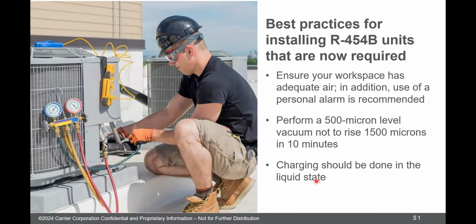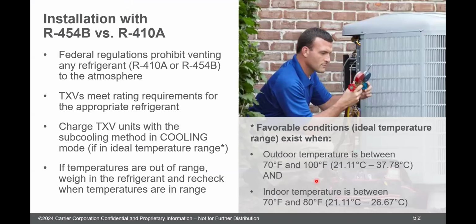Charging is done in the liquid state for 454B, just like it is done with 410A. That means when you charge, the tank gets turned over, so you're pulling refrigerant from the bottom, i.e. liquid, as opposed to the top where there would be vapor on there. So unlike R22, which was a single refrigerant, R410A and R454B are blends. So when it's a blend, we want to charge it in a liquid state. So nothing different there. From a charging standpoint, there's also nothing different.